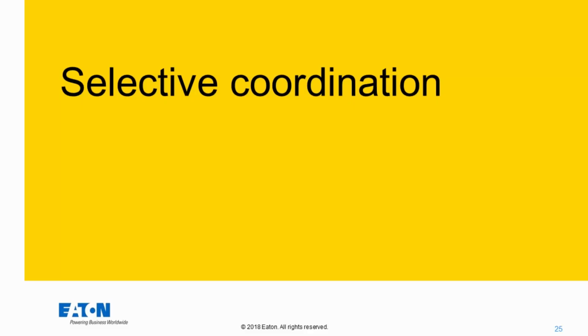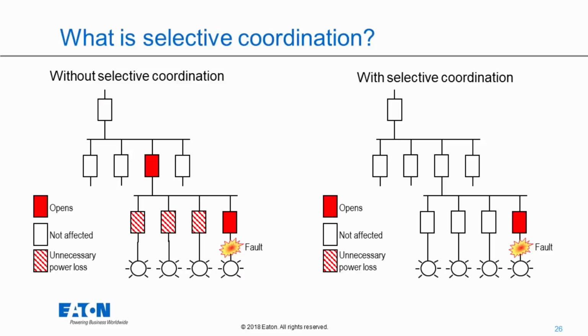We'll move on to selective coordination. So what is selective coordination? Selective coordination is quite simply the ability to localize an overcurrent condition. So if I have selective coordination, as we see on the figure on the right, the overcurrent device nearest that overcurrent condition is the only one that operates. So that will clear the fault in this case before the upstream device operates.